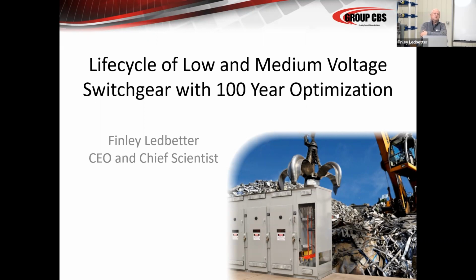That's a good thing. It's done a good job. It's going to continue to do a good job for us. And we're stuck with this technology for another 40 or 50 years. The reason being is, how do we go in and remove that gear without disturbing the cables? With all the build out that's been done around the switchgear, bus ducts, armor cable, steam pipes, whatever, it'd be nearly impossible to get to the gear to replace it. So really, we're kind of stuck with upgrade, life extension, and those sorts of things that we're going to talk about today and through these next 3 segments. The next 3 segments obviously will be more technical than what we're going to deal with today. Today, we're going to talk about the life cycle.